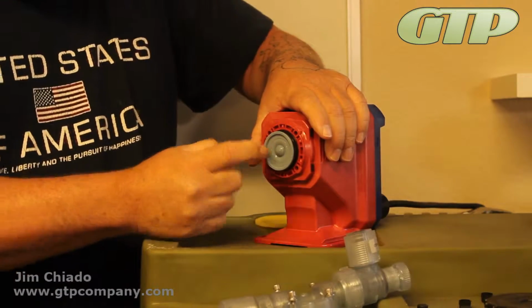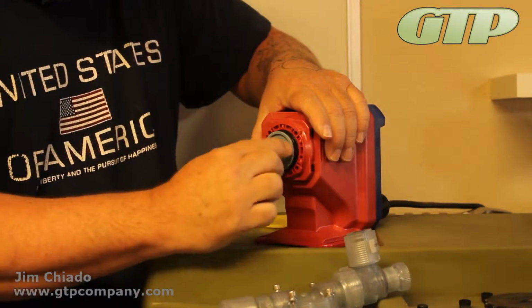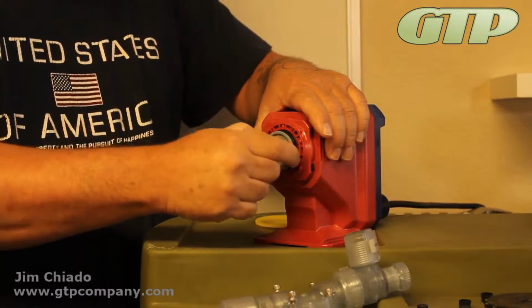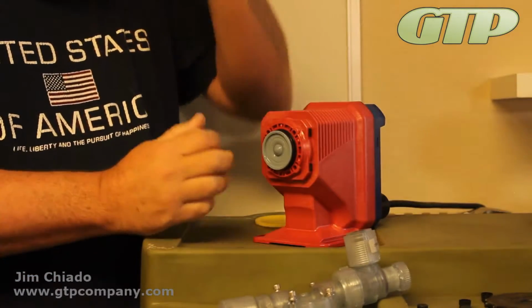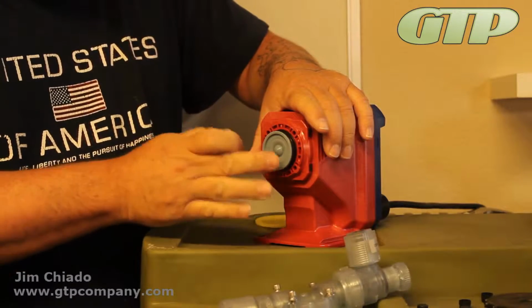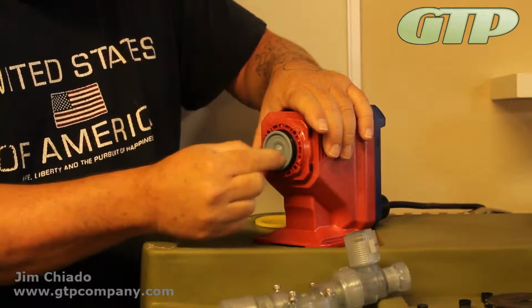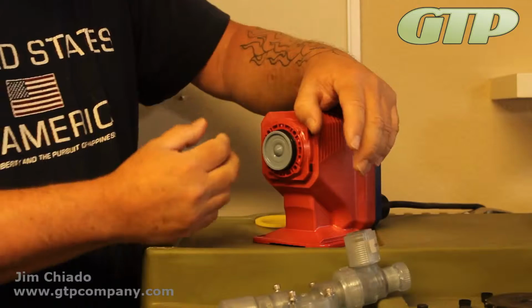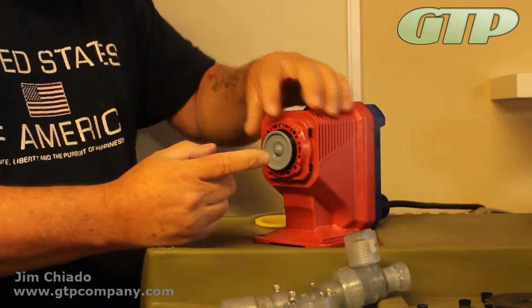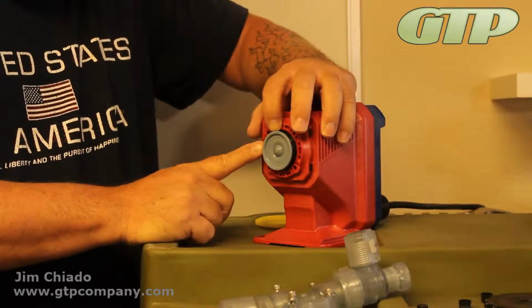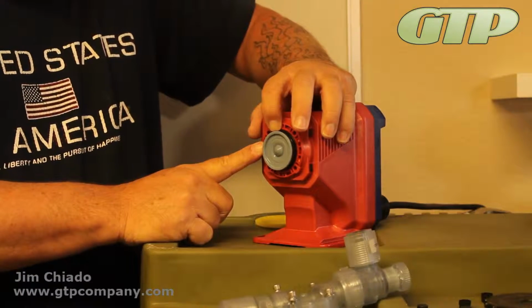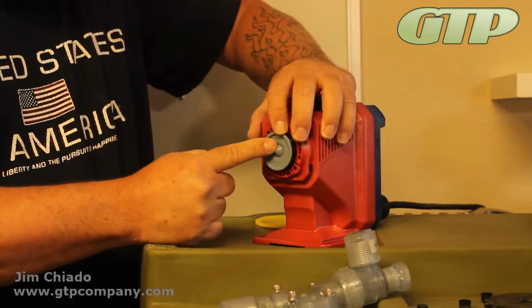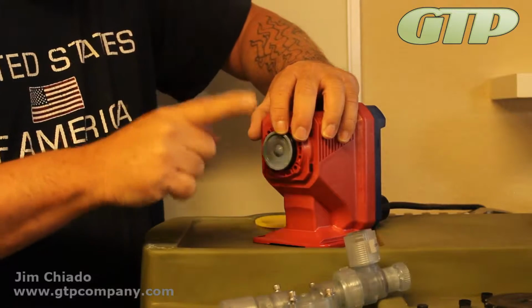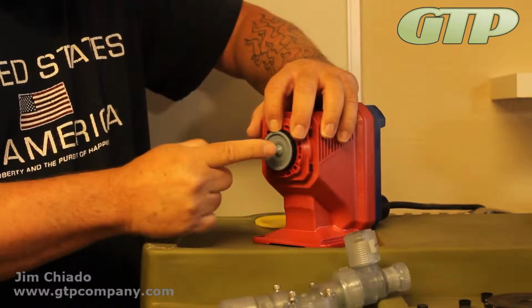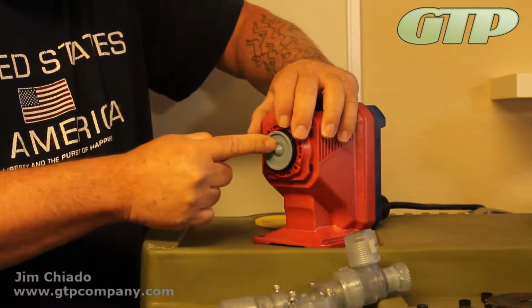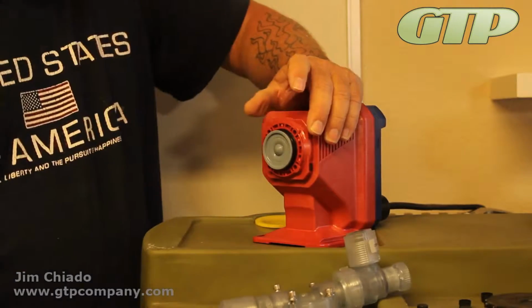When it delaminates, because this white face is glued to a rubber back or an EPDM backing, when it delaminates or comes unglued, you'll notice white - these white air bubbles behind there. What's happening is the pump is moving the rubber EPDM diaphragm in the back, but this part's not. Air and water are two different molecules, so you're moving the diaphragm, but this part just stays, so the pump won't prime.